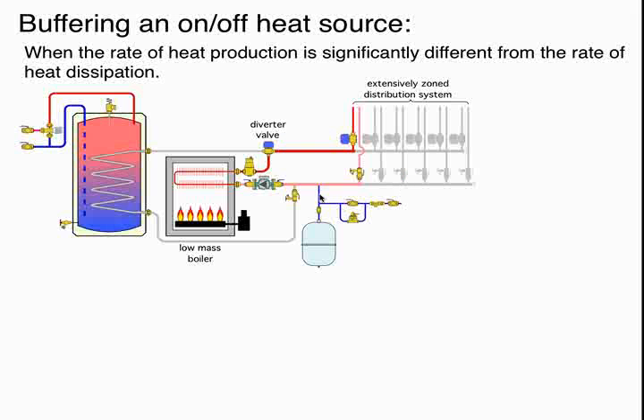Here's a possible piping schematic where we've got a low-mass boiler. Let's assume that this represents a copper tube boiler, relatively low metal content and water content compared to, let's say, a cast iron boiler. And we come out of that boiler, we have a diverter valve. We can either go to the left through an indirect water heater and then back through to the boiler, or if we have a call for space heating, we go to the right. And you can see over here we've got a lot of zoning going on. But the zones that you see there in gray, let's assume those zones are off.